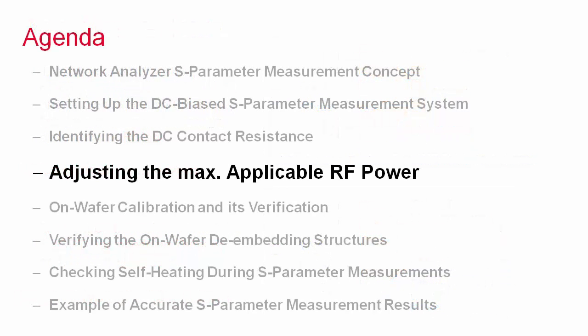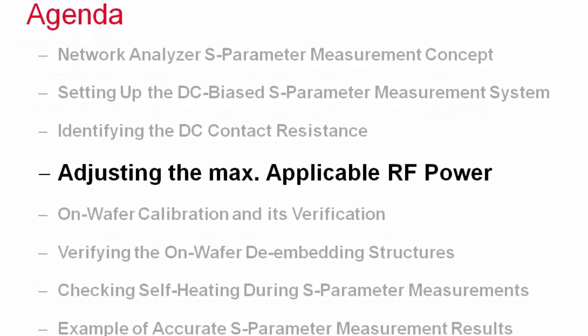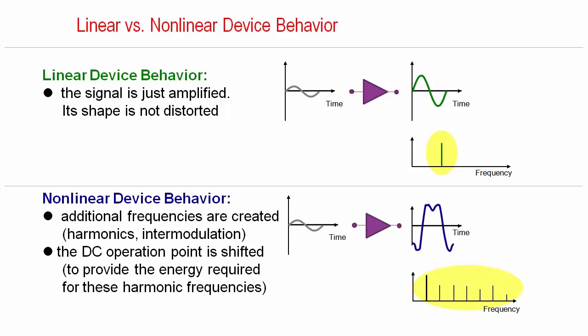Before starting the network analyzer calibration, we have to identify the maximum applicable RF signal power to ensure linear operation of the transistor. This means that during the measurement, the device is not overdriven and all signals are sinusoidal, represented by a single frequency only. A too large RF power would clip the signal and harmonic frequencies would appear. The analyzer, however, measures only the fundamental frequency, resulting in wrong S-parameters.